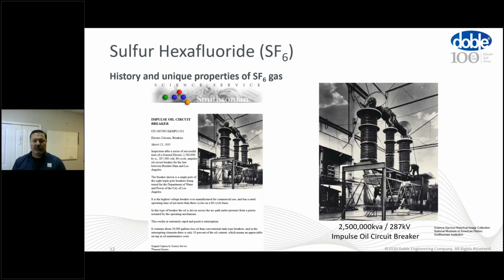This is a great piece of history here. This is a breaker, an oil circuit breaker put out by GE back in like 1935. It was a breaker installed to protect the line between Boulder and the city of Los Angeles. 2.5 million kVA at 287 kV impulse oil circuit breaker. What made this breaker special was its speed. You know, it was able to basically break or operate under a 60 cycle timing. So really interesting, unique in its time. But you can see the size of it in the picture on the right here. If you see my mouse, that's the individual working on it. You see the size of that breaker is pretty big. And again, you can find more information with the National Museum of American History at the Smithsonian Institution.